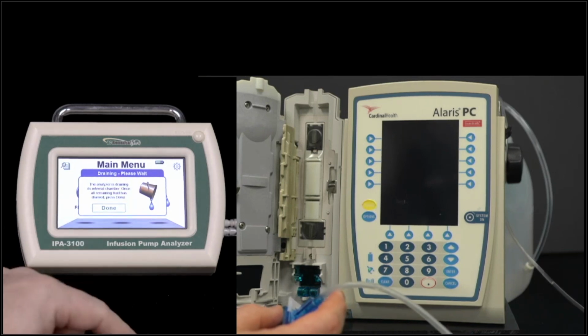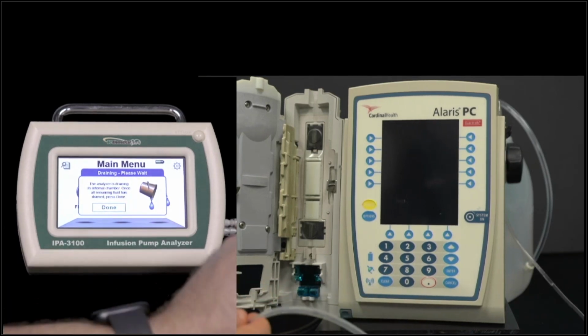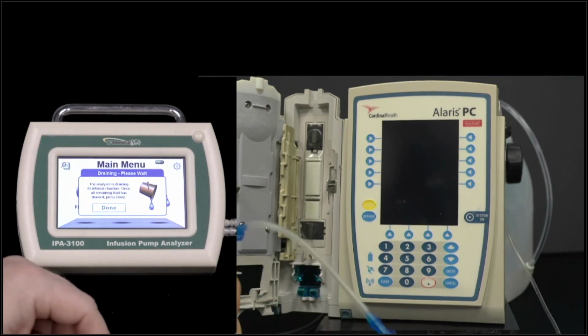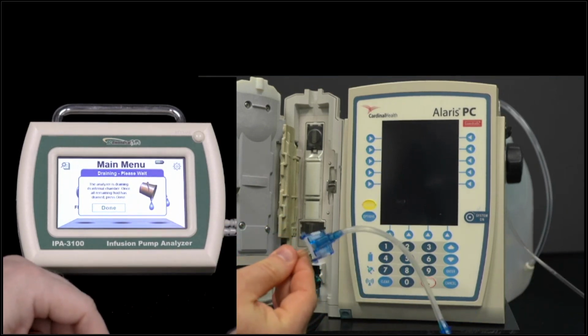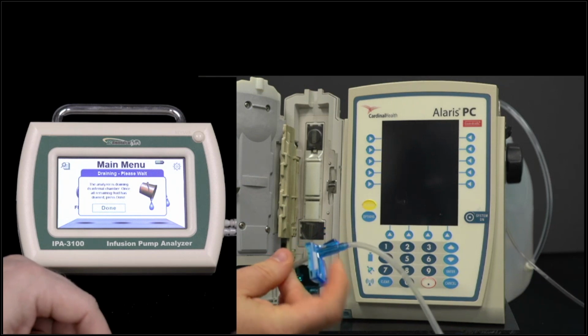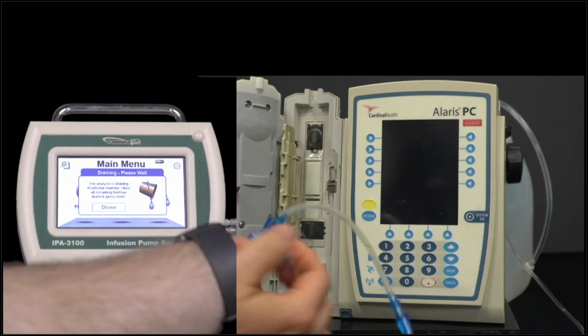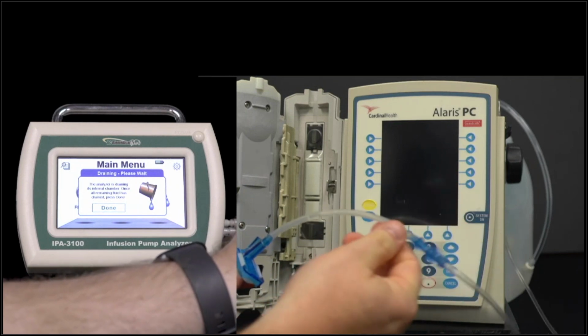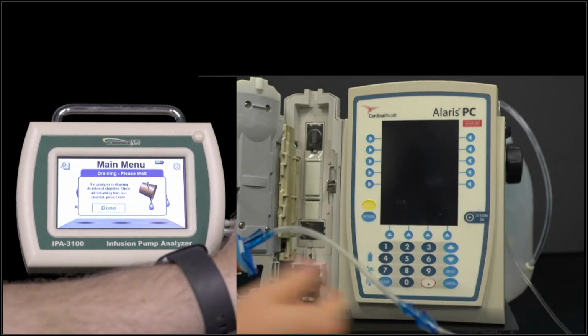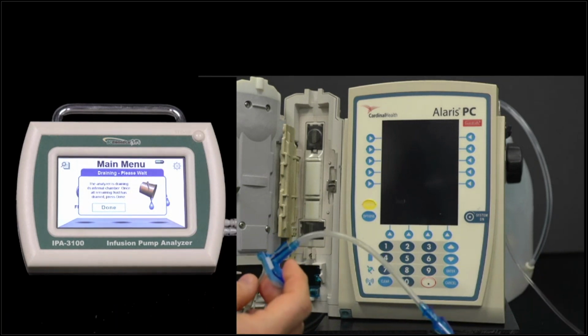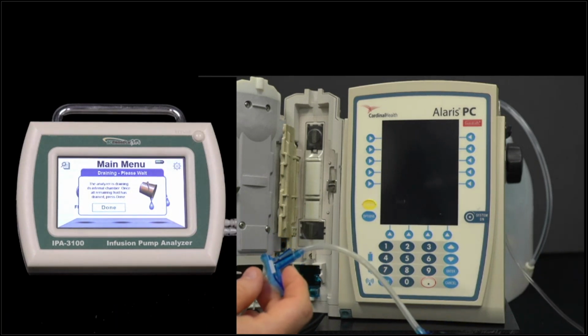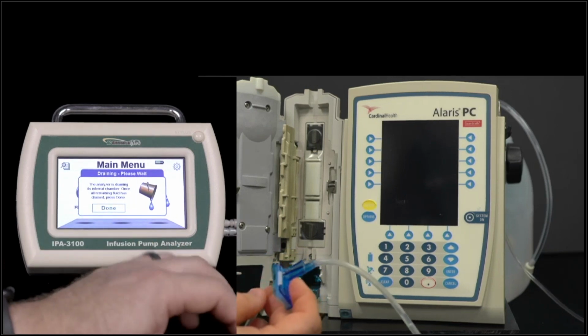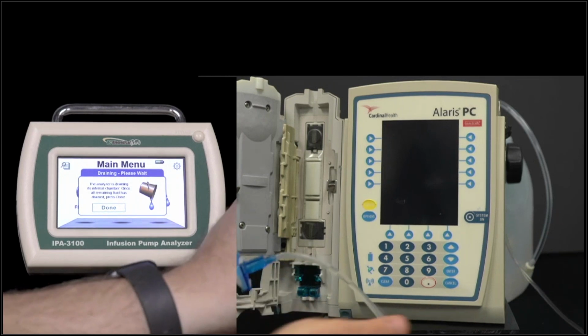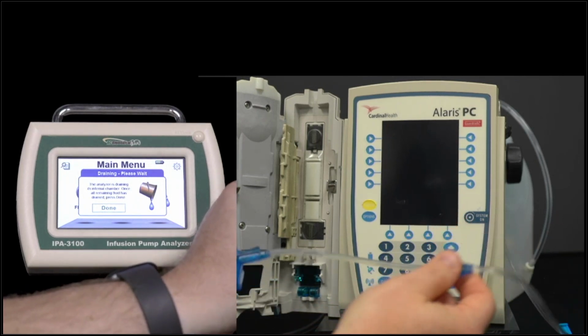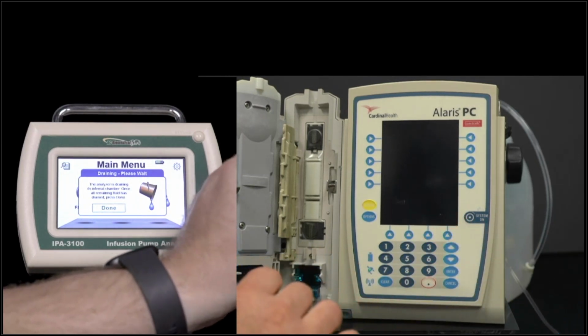So I go into the drain mode, and what that's going to do is, first I have to release the clamp here to allow the fluid to flow. I've opened the clamp, fluid can pass, and now we'll see all these little bubbles as we get all the air out of the line so the infusion pump won't yell at us during testing. I'm sure you've run pumps before, and if they see any air, they get really unhappy. So we're going to prime this tubing by using the drain mode on the 3100.